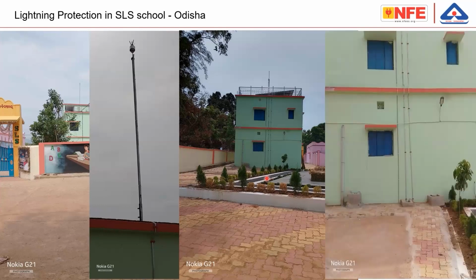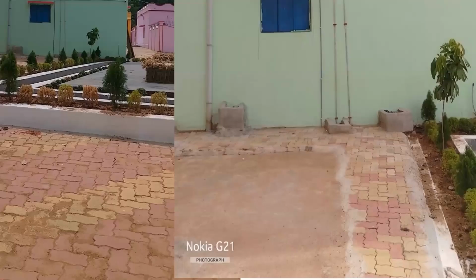Then the down conductors are connected to an earth electrode. As you can see here, there is a pipe or a plate or something like that, most probably a pipe. Each of the down conductors is connected to a rod, one down conductor connected to one rod. This is also illogical, and this is also a non-standard installation.